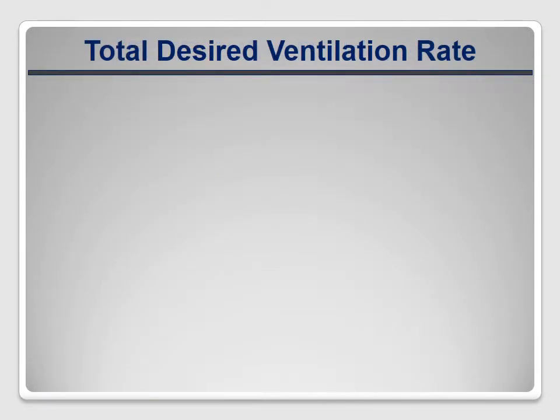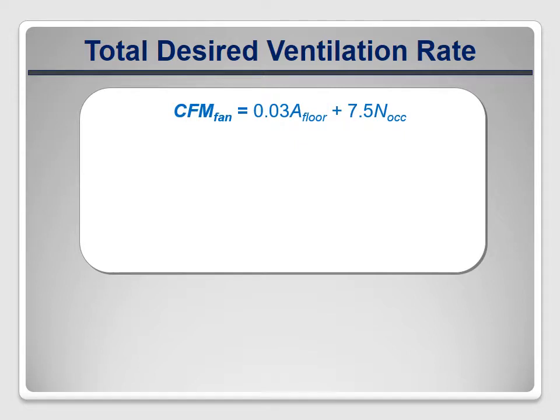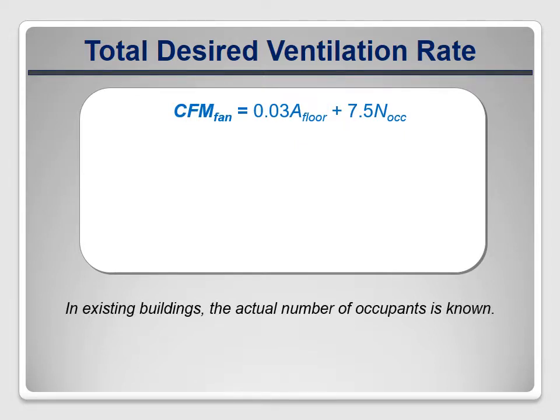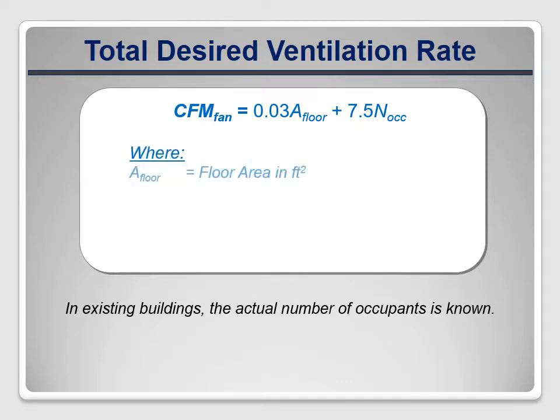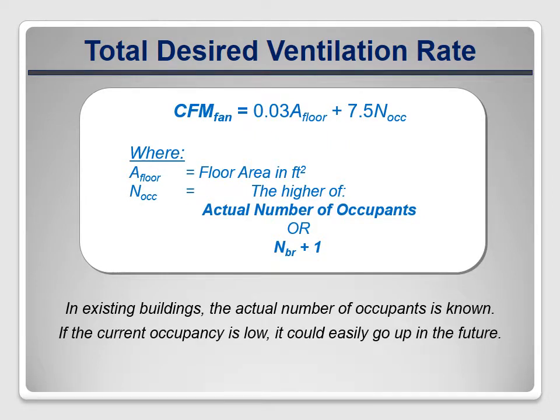There's also a change to the base equation. The total desired ventilation rate can now consider the actual number of occupants, since it's known in existing buildings. The standard says to consider the actual number of occupants and the number of bedrooms plus one — use whichever number is higher. This makes sense: if there are more people actually living in the house, provide more ventilation; but if current occupancy is low, base the rate on the number of bedrooms, since occupancy could easily go up in the future.